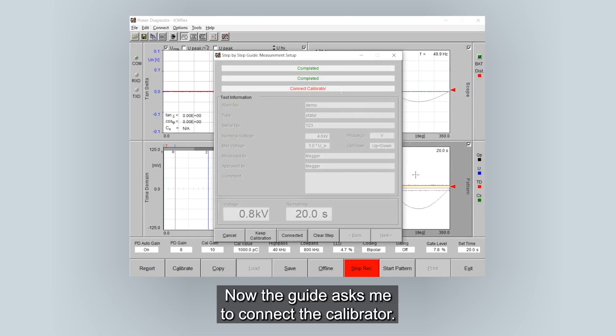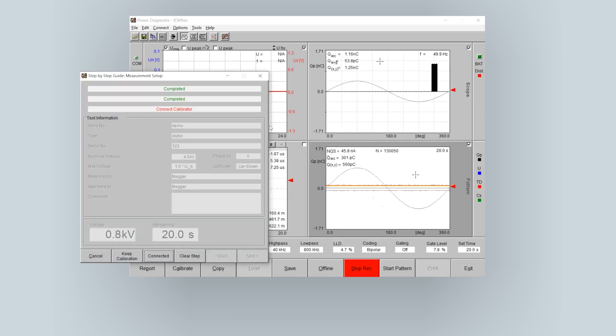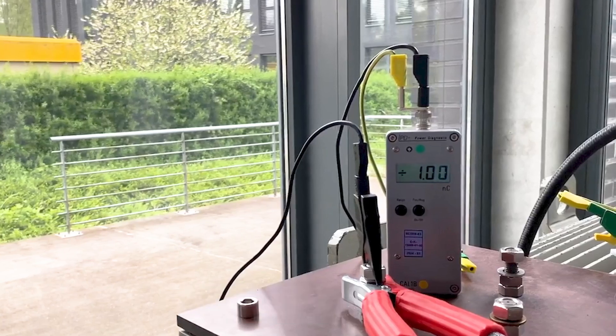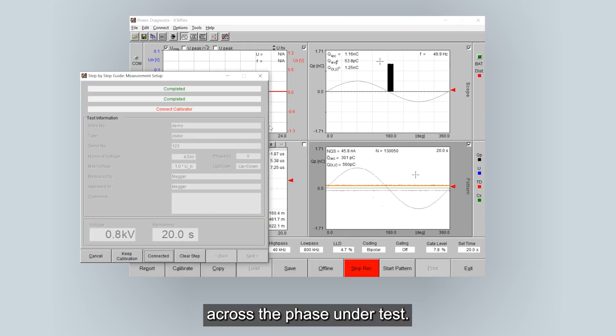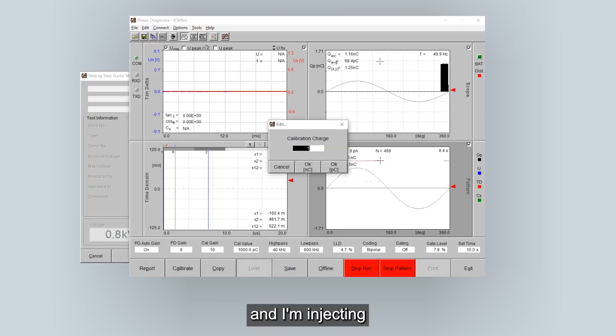Now the guide asks me to connect the calibrator. Now I will connect my calibrator across the test object. So now I've started injecting one nanocoulomb across the phase under test. Double click calibrator pulse and I'm injecting one nanocoulomb.